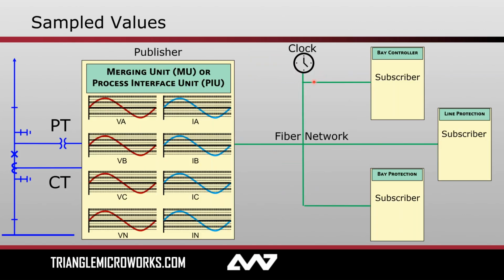We do this for not just one waveform, but 8, at least in a traditional 9.2 LE, and I'll define what that means in a moment, a 9.2 LE sample value system. So we have 4 currents, or 3 phases and neutral, and 4 voltages as well. Those are ultimately still coming in from CTs and PTs. Potentially, it could be optical measurements or something like that. But somehow we're getting in those samples, passing them out on a network, typically fiber, over to any and all subscribers.